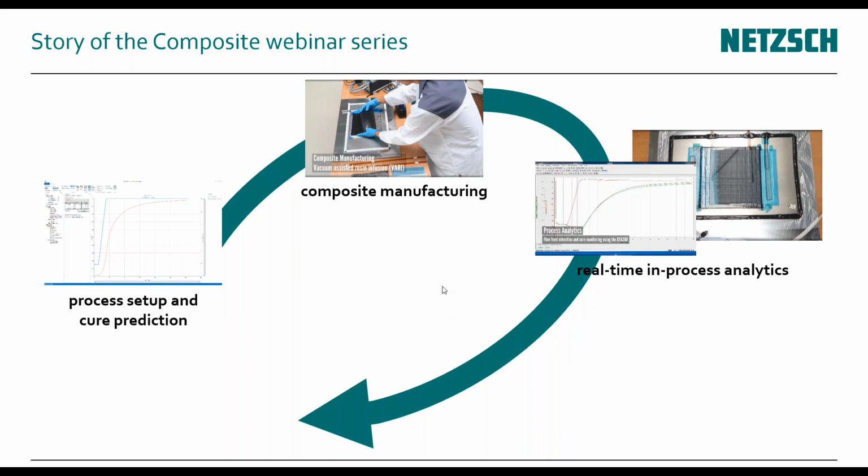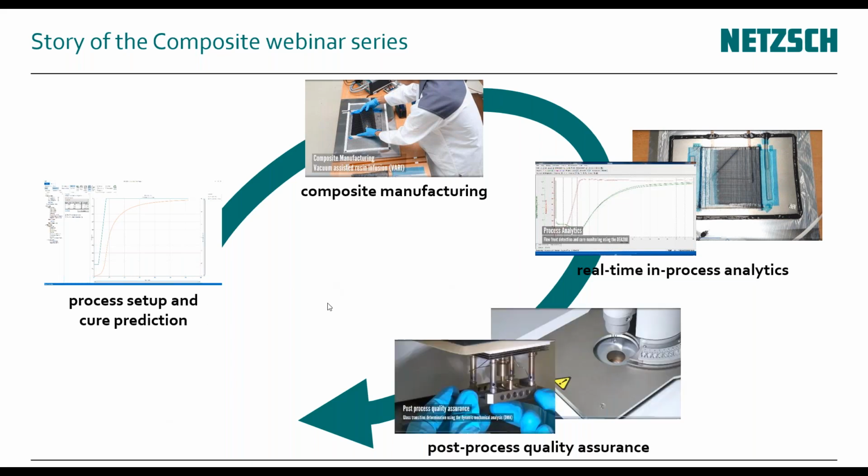As a third step, this is what my colleague Alexander Kalupka has shown you. We at NETZSCH have a sensor that uses dielectric analysis, which we can use for real-time in-process analysis of the curing. So we have a sensor that traces the curing inside of your process. And as a fourth step, we have to do some quality assurance.